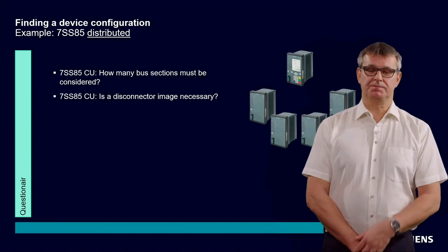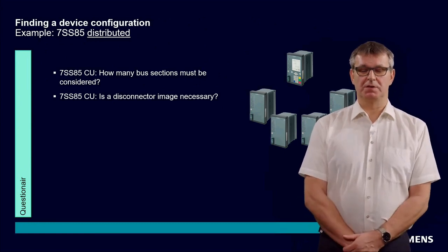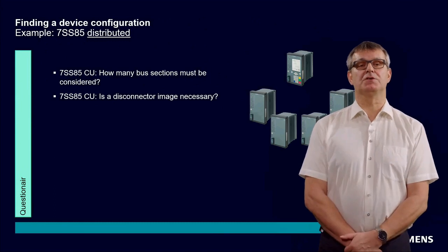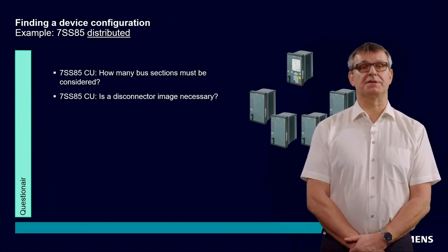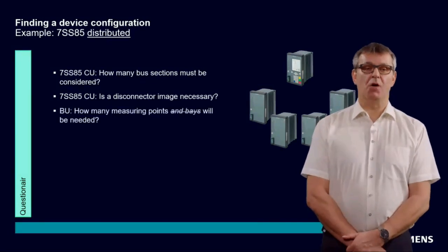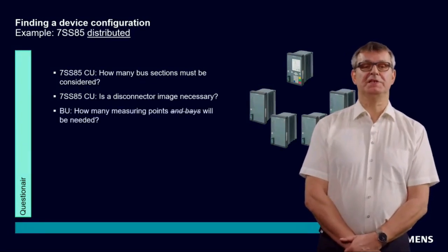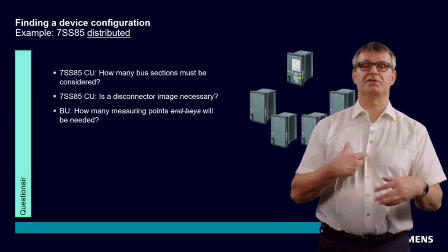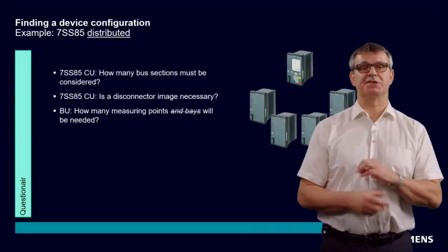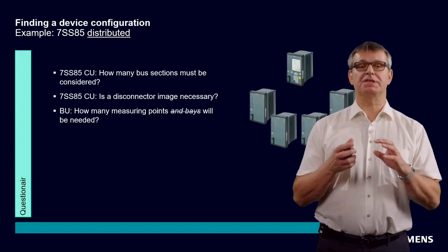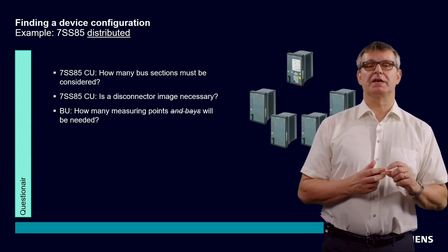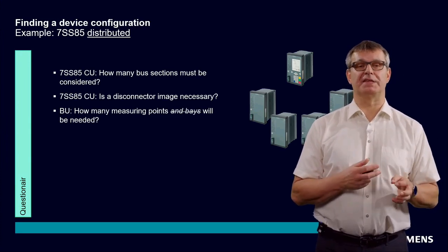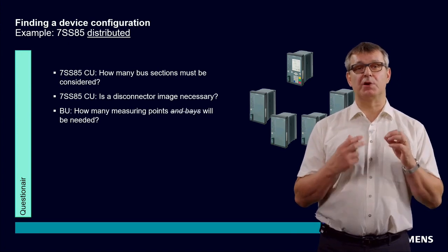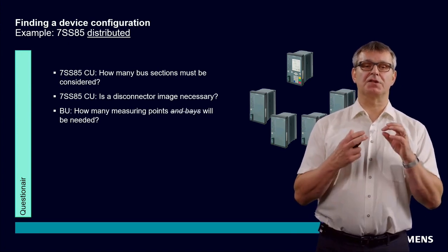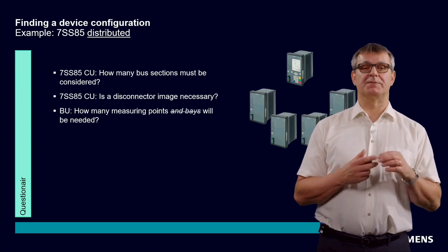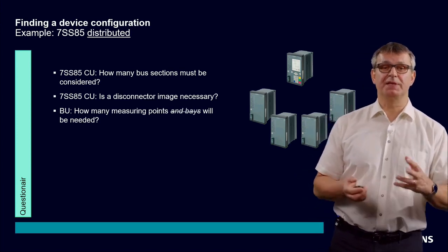Do we need a disconnector image? The same as before, this is also necessary only to find the correct type of the 7SS85 CU. How many measuring points and bays will be needed? As already said, the number of bays is struck out here, because in the fully distributed approach it's not necessary anymore to count the number of bays. You only have to count the number of measuring points, and of course, the measuring points will be located, and must be located, in the bay unit.